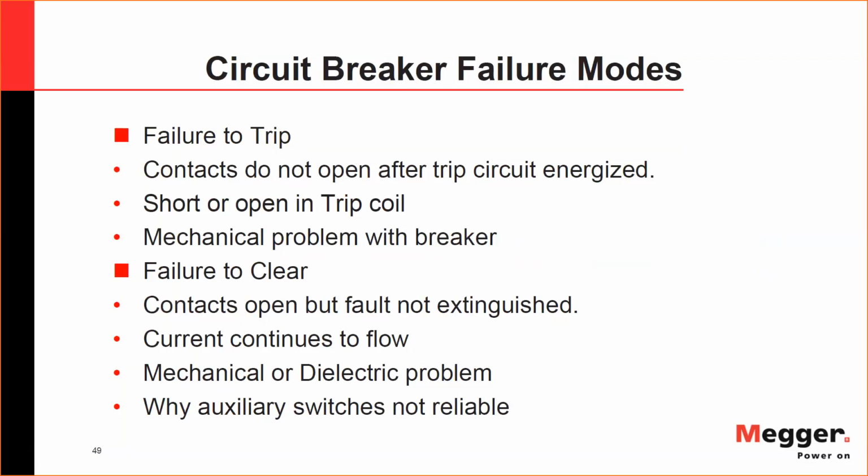Now, there is a different mode of failure, where the breaker has operated. It starts moving to open the contact, but for some reason, the fault did not extinguish. It was still existing even after the poles have been opened. The current still flows. That's why the current detector element is very important in this case.